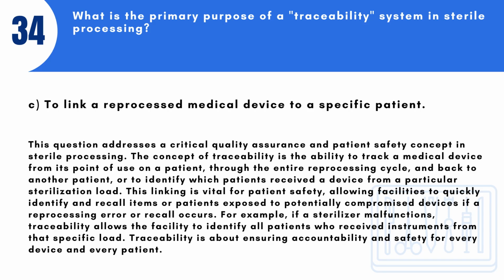particular sterilization load. This linking is vital for patient safety, allowing facilities to quickly identify and recall items or patients exposed to potentially compromised devices if a reprocessing error or recall occurs. For example, if a sterilizer malfunctions, traceability allows the facility to identify all patients who received instruments from that specific load. Traceability is about ensuring accountability and safety for every device and every patient.